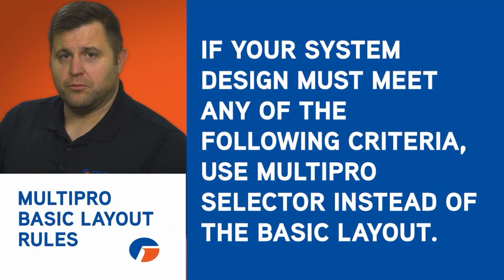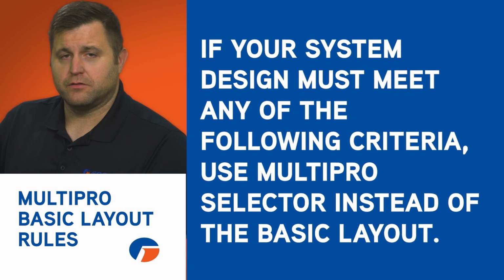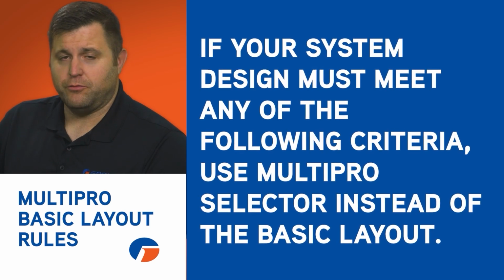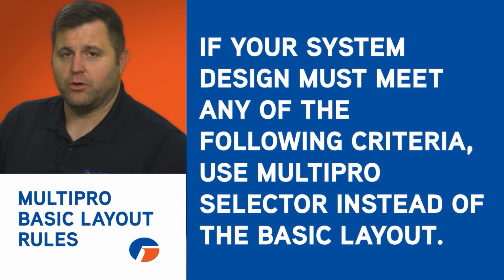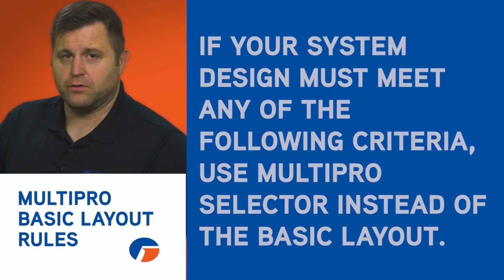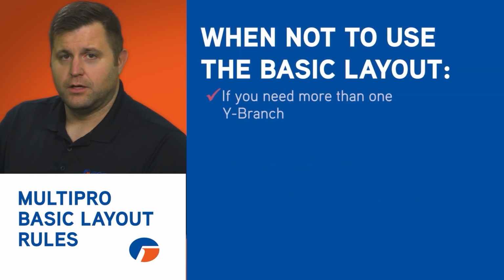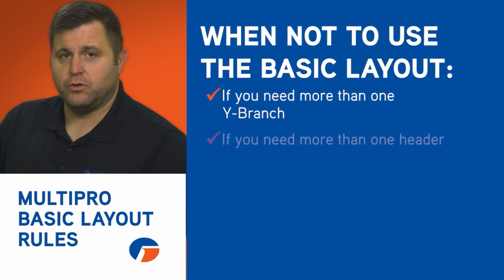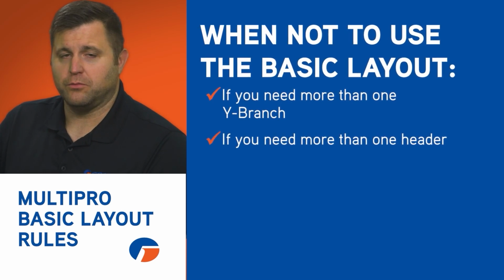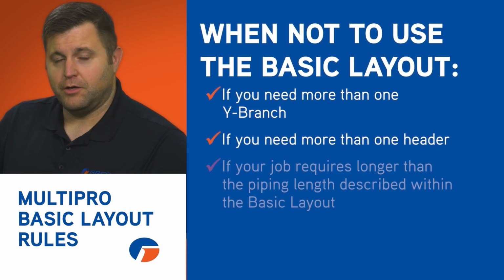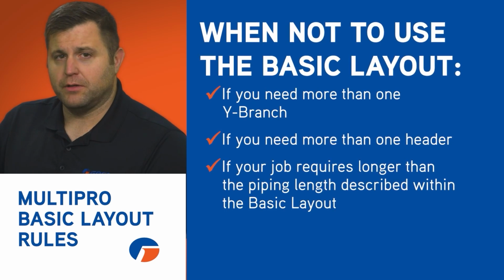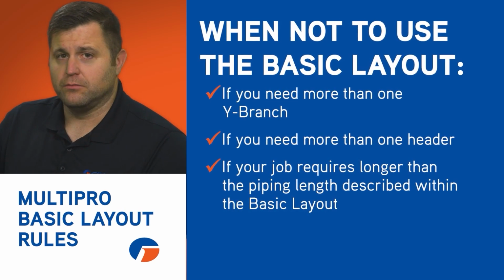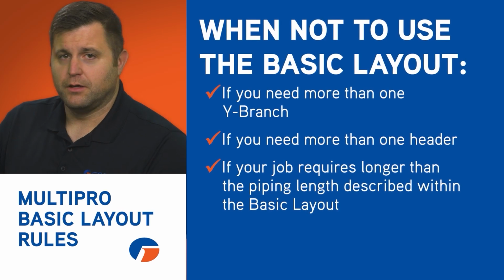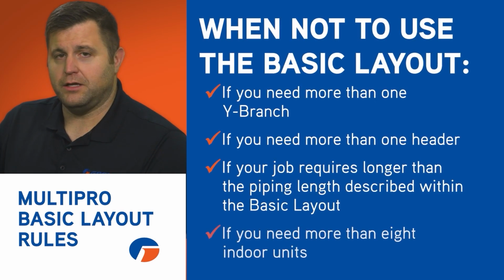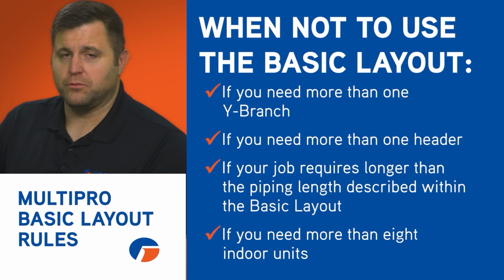Before going on to talk about when you'll use the basic layout, let's discuss when you wouldn't. If your system design must meet any of the following criteria, you'll use MultiPRO Selector instead of the basic layout. If you need more than one Y branch, or if you need more than one header, you'll use the MultiPRO Selector. If your job requires longer than the piping length described within the basic layout, you'll use the MultiPRO Selector. Finally, if you need more than 8 indoor units, you'll again use the MultiPRO Selector.